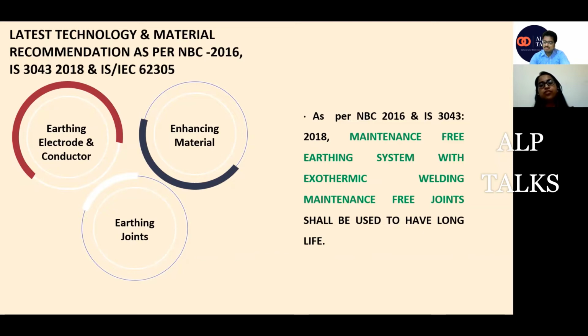Basically, the core is of mild steel only, and it has a minimum copper coating of 250 microns. The manufacturing standard is UL listed, UL 467. As per that, the copper coating has been done on the MS rods. So what happens? We get the conductivity of copper, we get the corrosion resistant properties of copper, and also we get the strength of steel. By combining copper and steel, we reduce the cost too. That's true, otherwise it is more costly with copper.